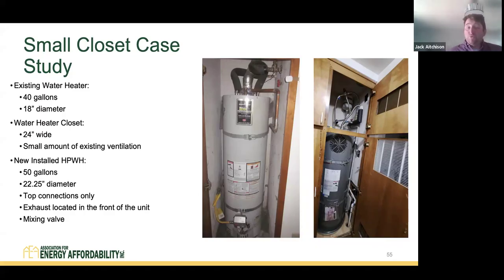So the existing water heater is 40 gallons, 18 inches in diameter. That's extremely small. And like I mentioned, most heat pump water heaters are going to be larger because the process of heating that water takes a little bit longer. So we want more storage volume to make sure that we don't run out of hot water. The water heater closet was 24 inches wide. Again, probably the smallest size of closet that we typically see in a multifamily building. There's a small amount of existing ventilation, but we had to add more.